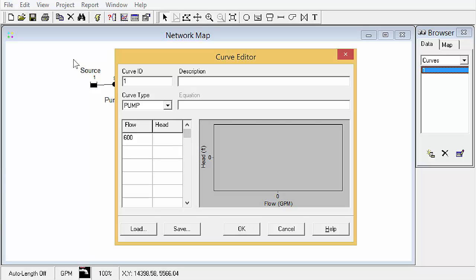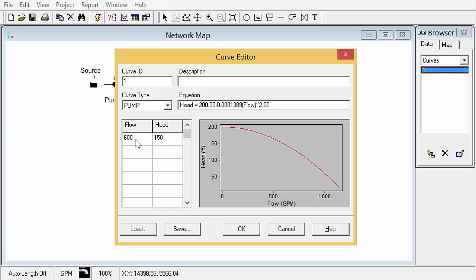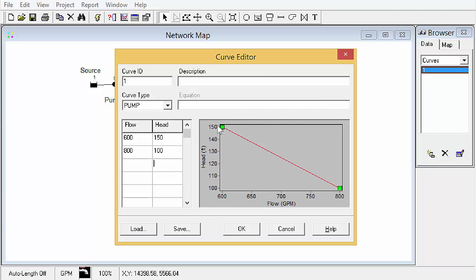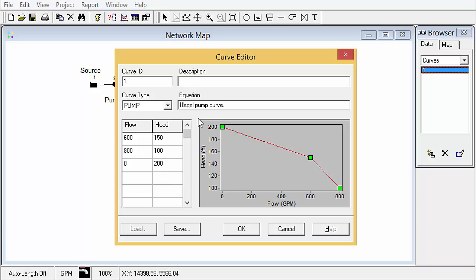And all we have to do is type in our data points here, 600 GPM at 150 feet of head. Now, when we only have a single point in here, it gives us a nice curve there based on a default equation that's built into EPANET. If we were to add more points, as soon as we do that, it's just going to do a point to point and then EPANET will interpolate values between all the different points. So I could put zero flow here and we can do 200. And that will do us a nice three point curve, several ways you can accomplish that.